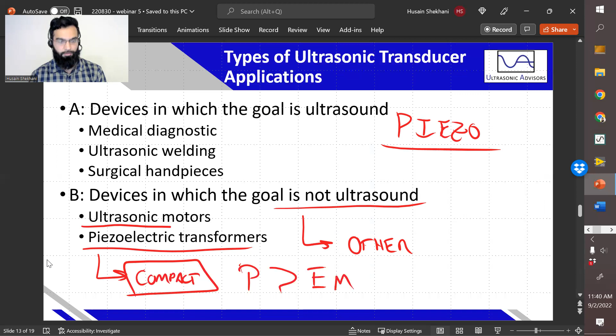I'll just describe a couple of applications. Here's an ultrasonic resonator, which goes into a phacoemulsification handpiece for cataract surgery. You put a needle at the tip, and here's a simulation of what it looks like, and a half cut of that. The piezoelectric transducers, or ceramics, are driven. There's high amplitude at the tip, and a lot of gain due to both resonance and the necking down of this oscillation to a tip.